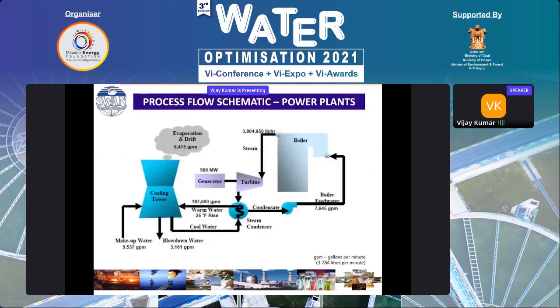See, actually, if you look at power plants earlier, TOC was not a parameter. You normally came across silica, sodium, cationic conductivity, dissolved oxygen, and conductivity. These are the terminologies you normally come across.